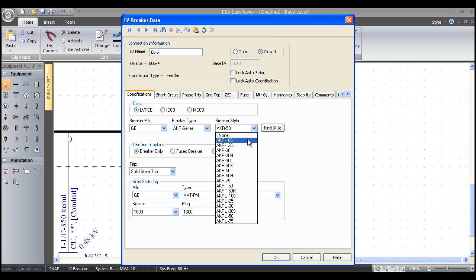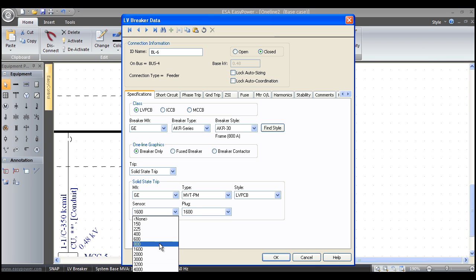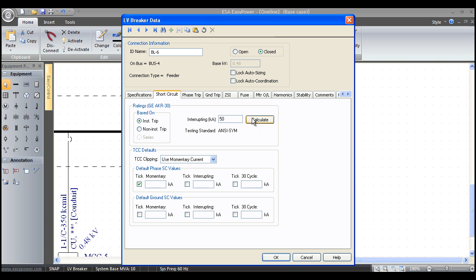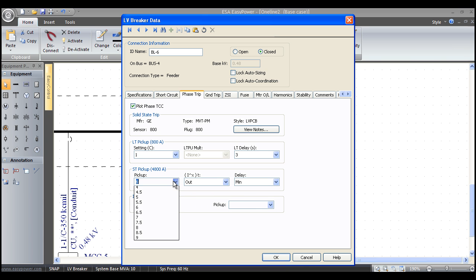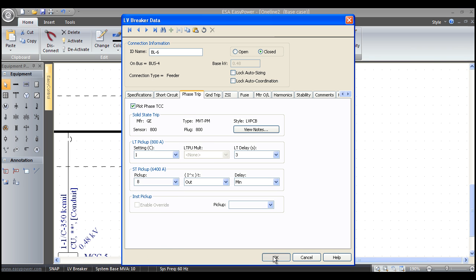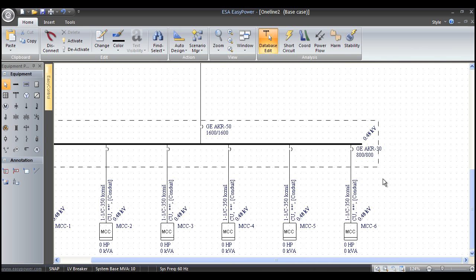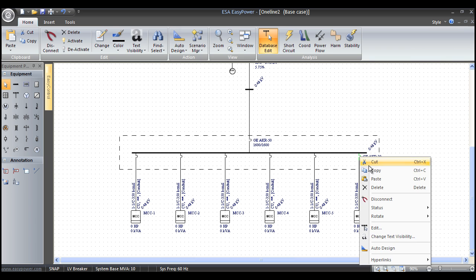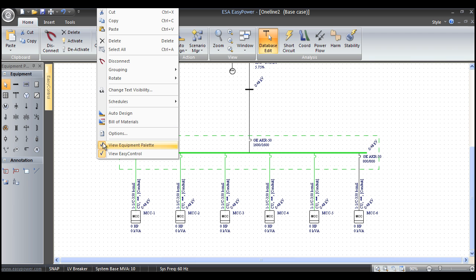We probably need to make this an AKR30, it's probably a smaller feeder breaker, so we just change this to AKR30. We change our sensor to 800 amps, our plug to 800, our short circuit rating changes, our phase trip settings probably change slightly, and there's our unit. We just right mouse click, copy, left mouse click, press slide release, right mouse click, paste, and there's an entire switchgear lineup in two mouse clicks.